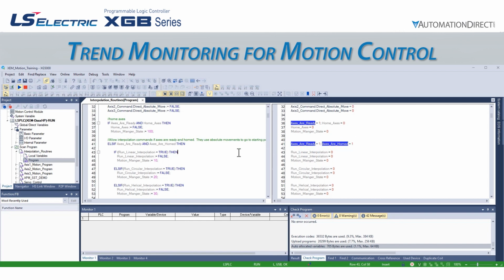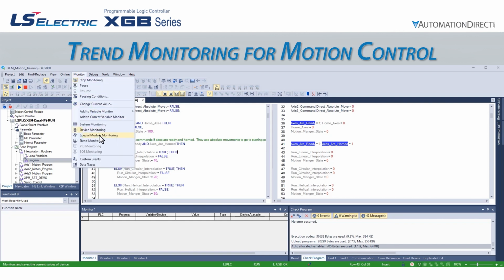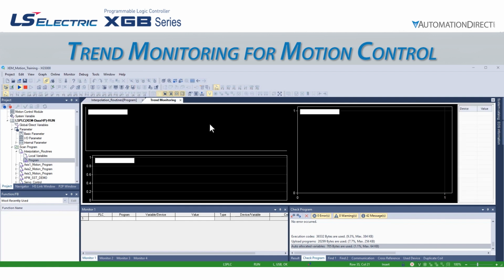To start trend monitoring, we can go to Monitor, Trend Monitoring, or click on the icon of a graph in the toolbar. This opens the Trend Monitoring tab in the main project window. The tab has 3 areas for data monitoring. The upper left corner displays the bit graph, which is useful for monitoring Boolean data from the project. The lower left displays the trend graph, which is useful for monitoring numerical data. The right side displays the XY graph, which can display 2 data points at the same time for comparison. Because the bit graph is straightforward and the same principles apply to it as to the trend and XY graphs, we won't cover it in detail.